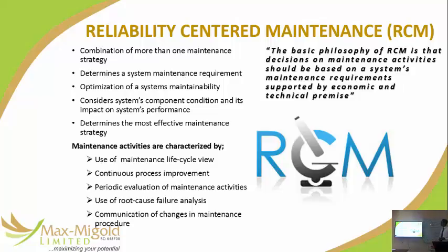Reliability-centered maintenance is the last one we're going to look at. It's actually a combination of more than one maintenance strategy. It is a system that allows you to take all your assets and all your equipment in your portfolio, and then assign various strategies to them and analyze the cost of those strategies. You are looking for the cheapest overall cost. So you are juggling strategies, and then using that juggling to balance out the cost on an asset by asset basis while watching the total overall cost.